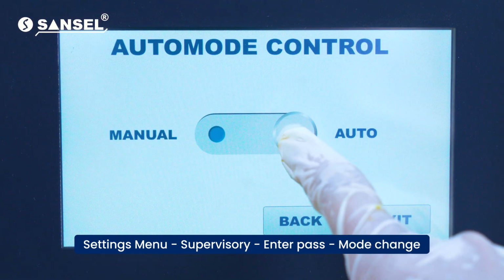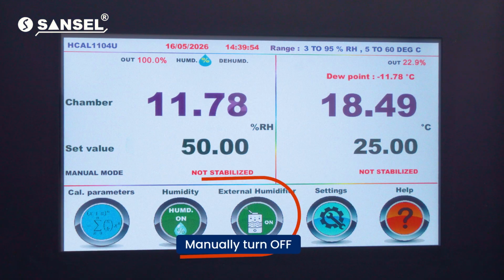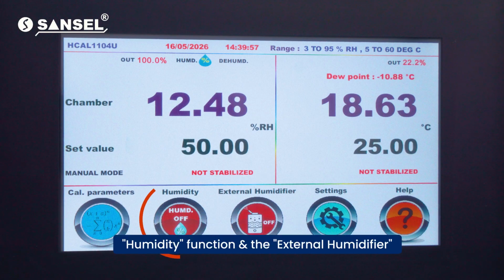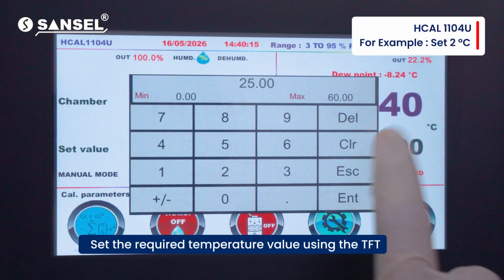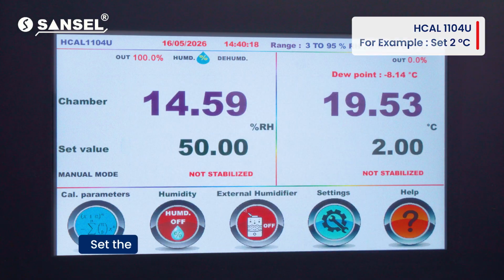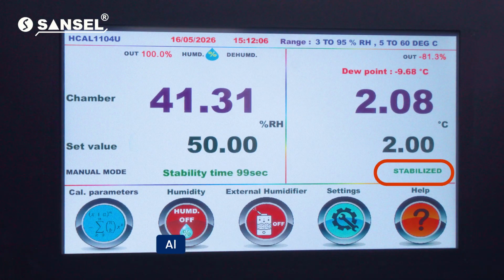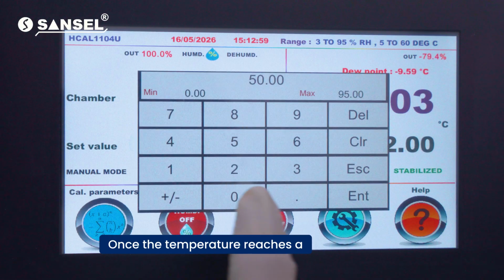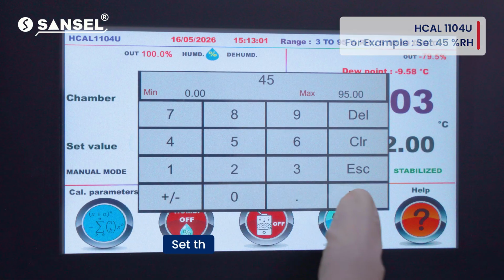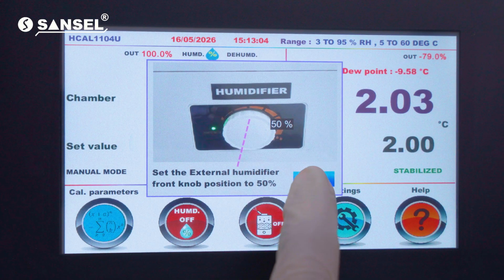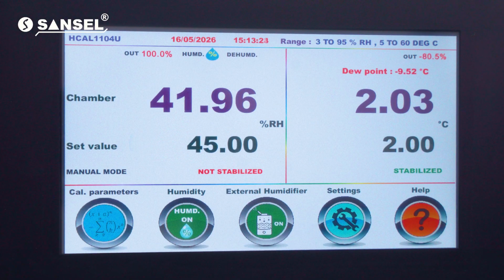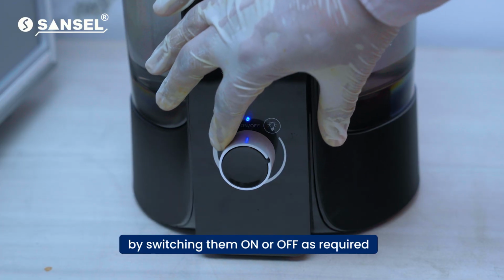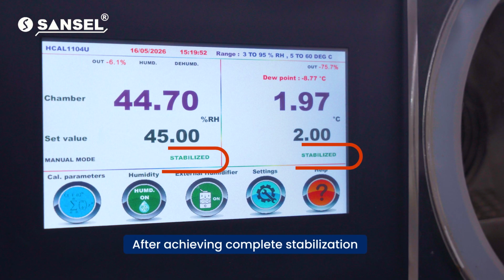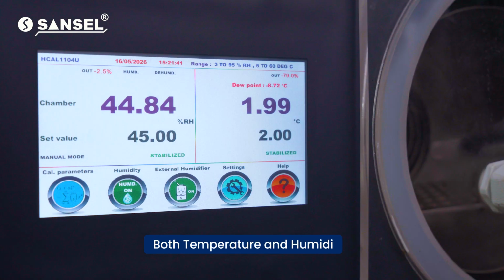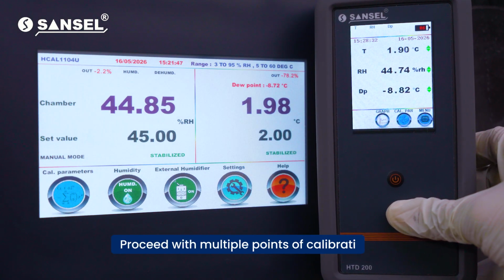Manual mode operation. Manually turn off both the humidity function and the external humidifier. Set the required temperature value using the TFT display and allow the system to stabilize. Once the temperature reaches a stable condition, set the desired humidity value. Now, based on the on-screen guidance, manually control the humidity and external humidifier by switching them on or off as required. After achieving complete stabilization of both temperature and humidity, proceed with multiple points of calibration.